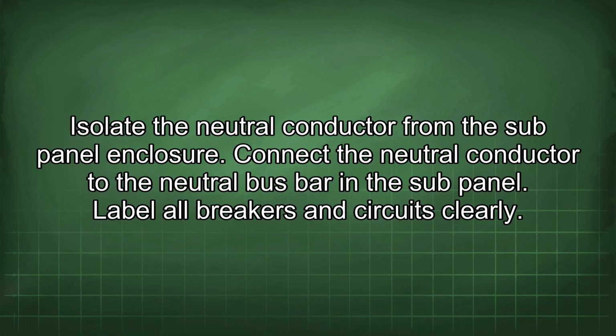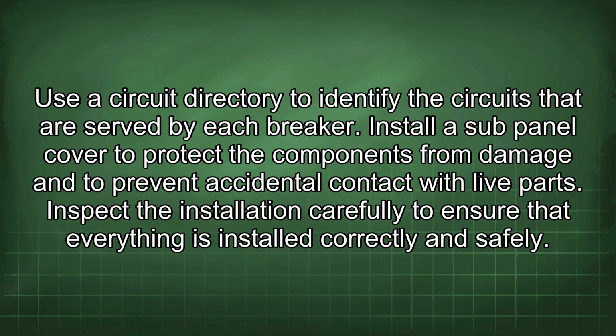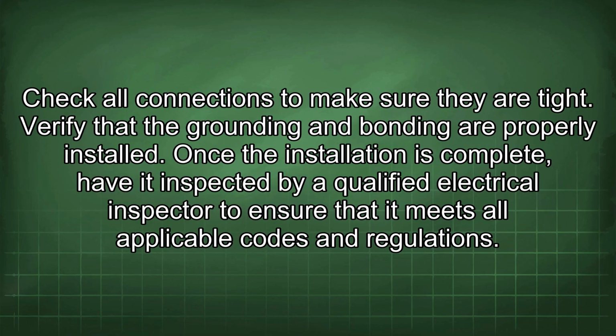Label all breakers and circuits clearly. Use a circuit directory to identify the circuits that are served by each breaker. Install a sub-panel cover to protect the components from damage and to prevent accidental contact with live parts. Inspect the installation carefully to ensure that everything is installed correctly and safely. Check all connections to make sure they are tight. Verify that the grounding and bonding are properly installed.